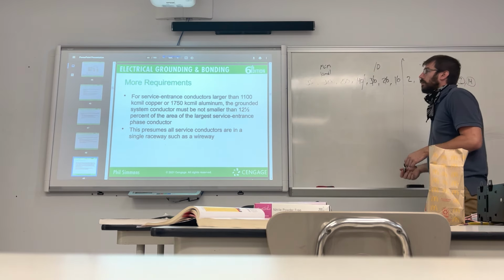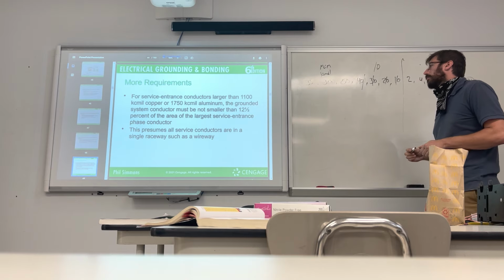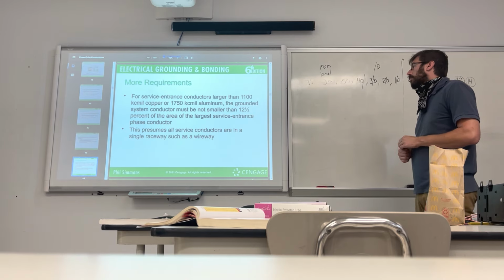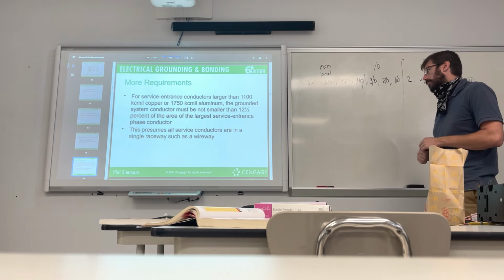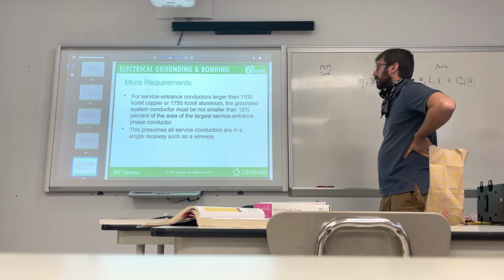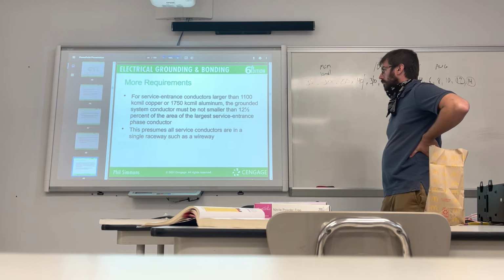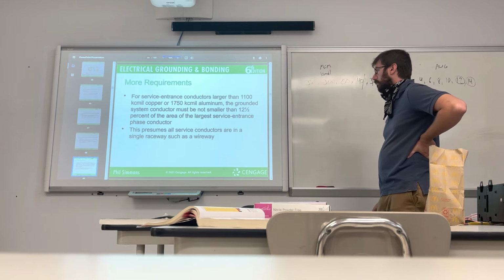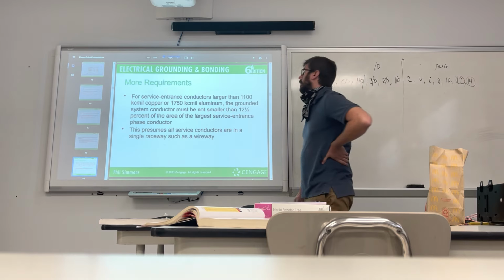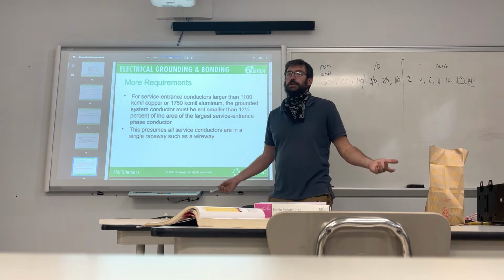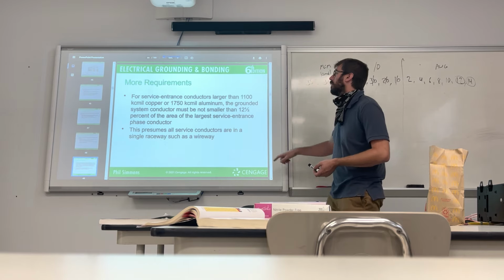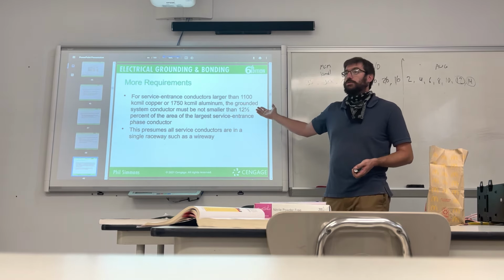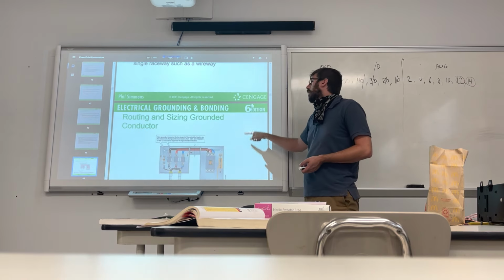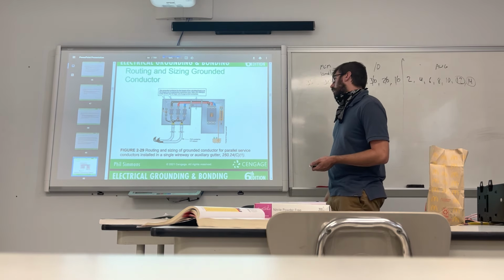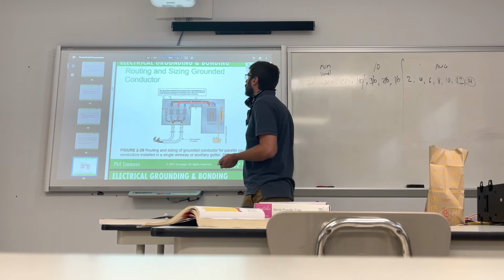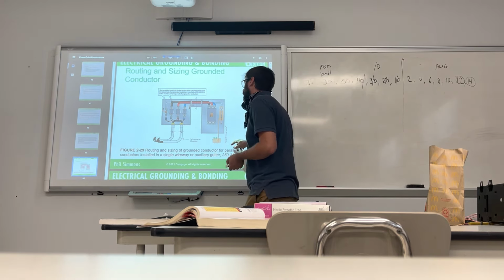More requirements. For service entrance conductors larger than 1,100 kcmil copper or 1750 kcmil aluminum, the grounded system conductor must be not smaller than 12.5% of the area of the largest service entrance phase conductor. This presumes all service conductors are in a single raceway, such as a wireway. Well, once again, the book starts getting complicated, like "must not be smaller than." Couldn't you say "must be larger than"? Must not be smaller. The book is just very confusingly written. But once again, like I said, at a certain point, the 12.5% rule comes into play. Let me try and get out here. Oh, it's 12.5%. Okay, we just covered that.